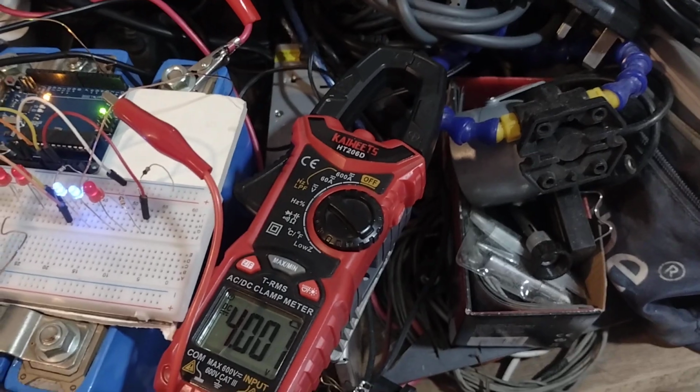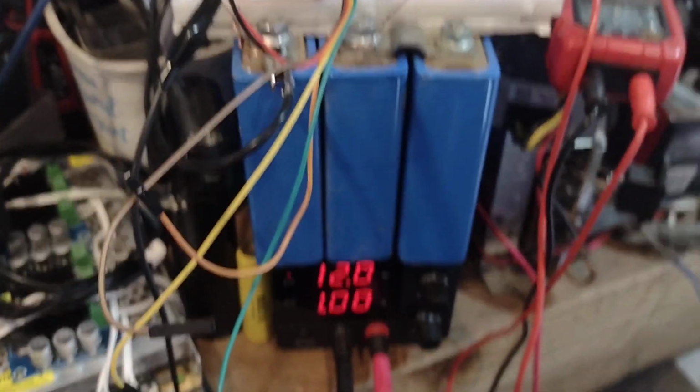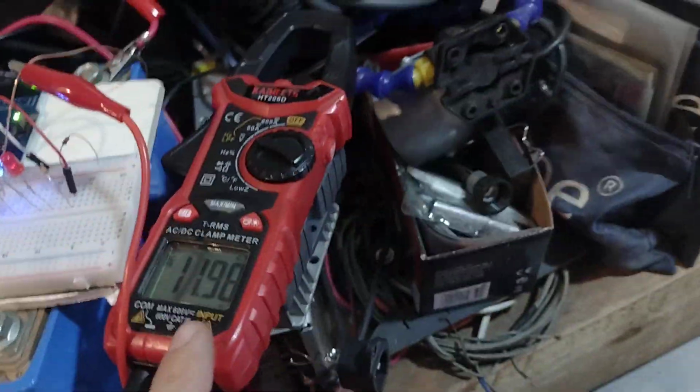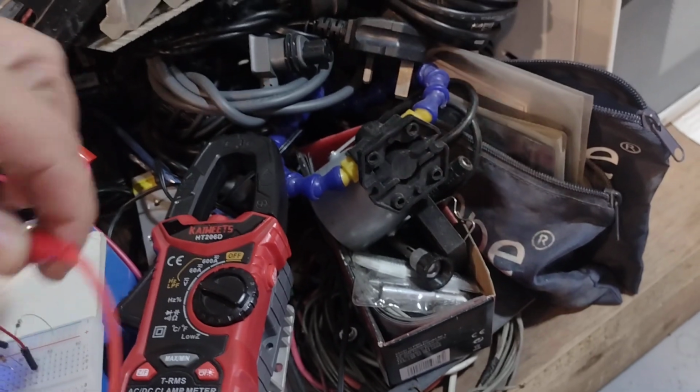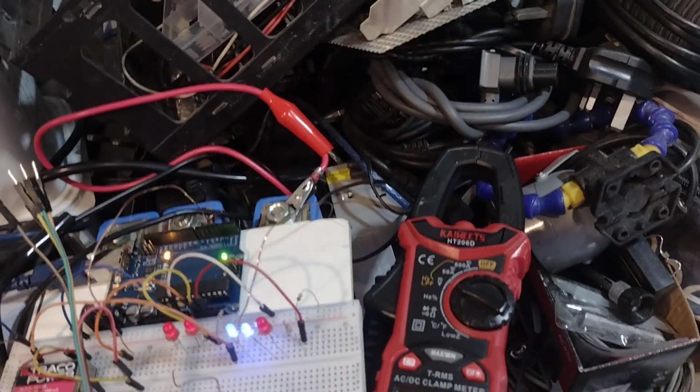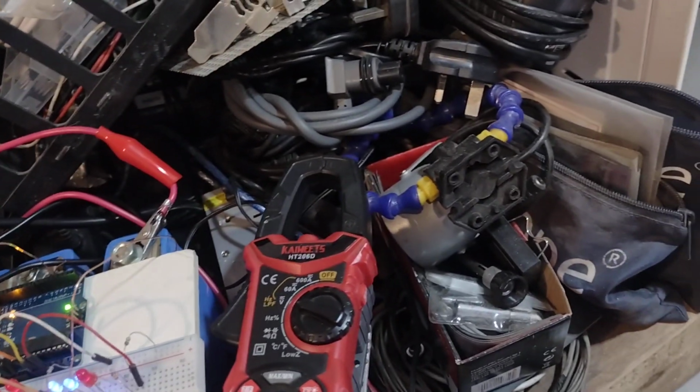There we go, so it's not in the way. Yeah, but the cell balancer is obviously working, isn't it? Let's see what the full voltage actually is now. 11.98. Yeah, so that actually is more aligned with the power pack itself. So the first cell, which goes into there, doesn't it? Yeah. So the first cell is actually 3.9.